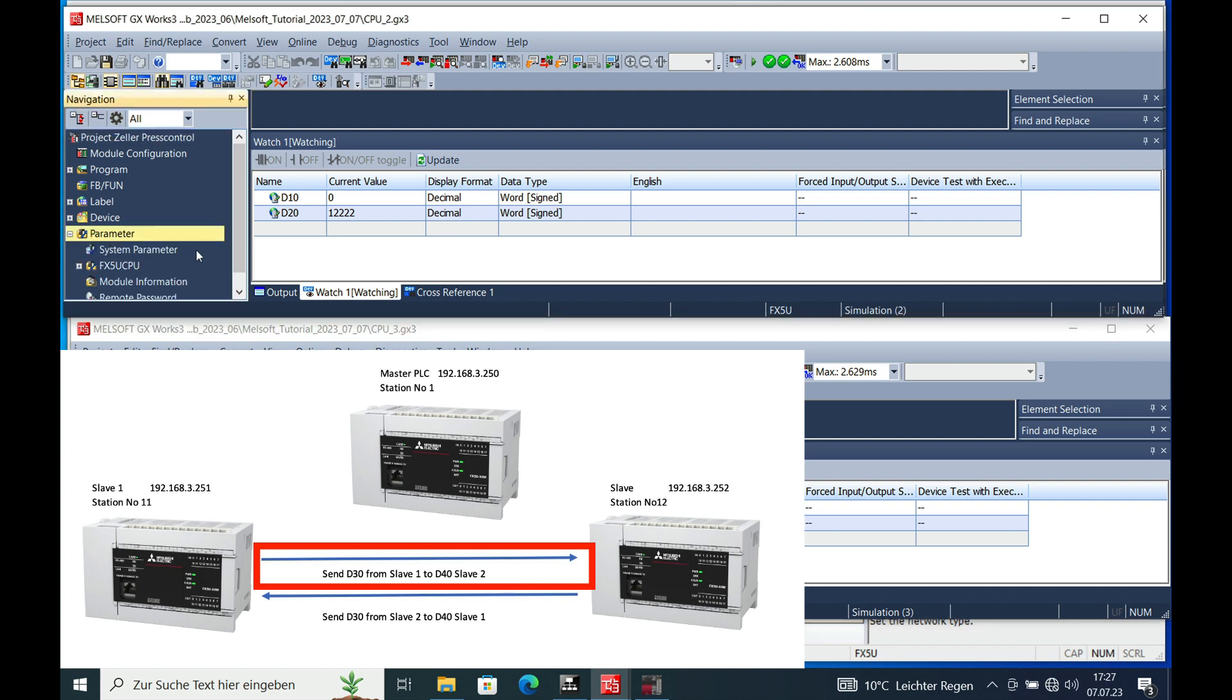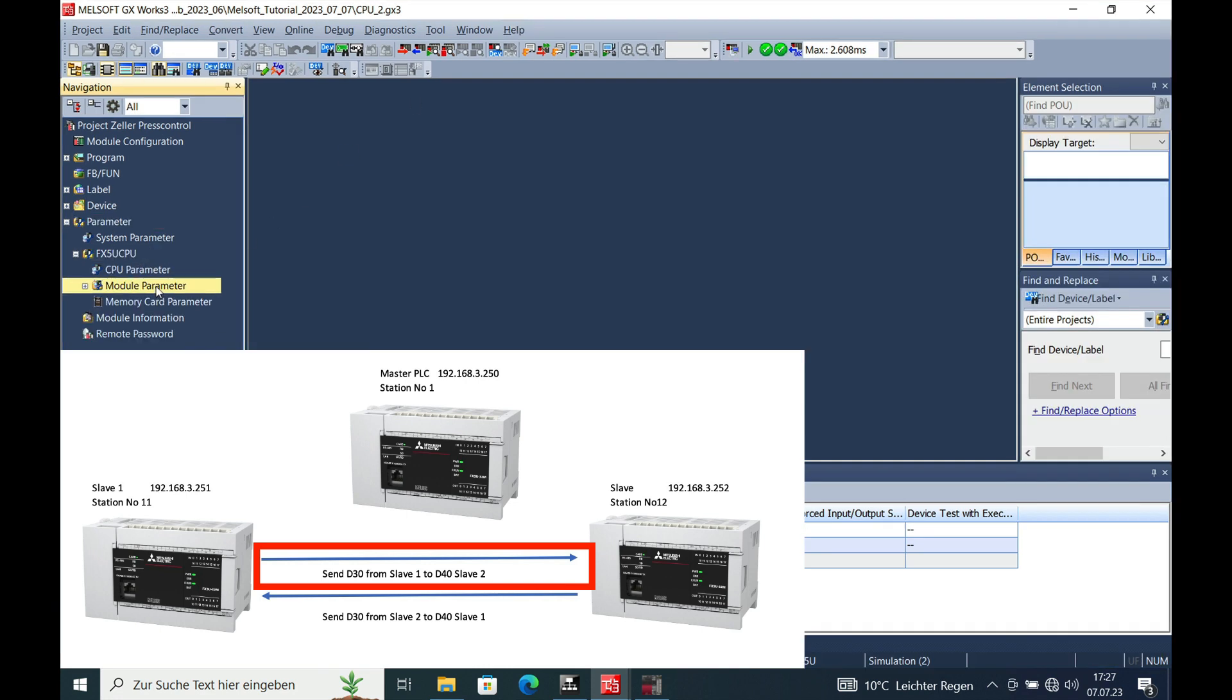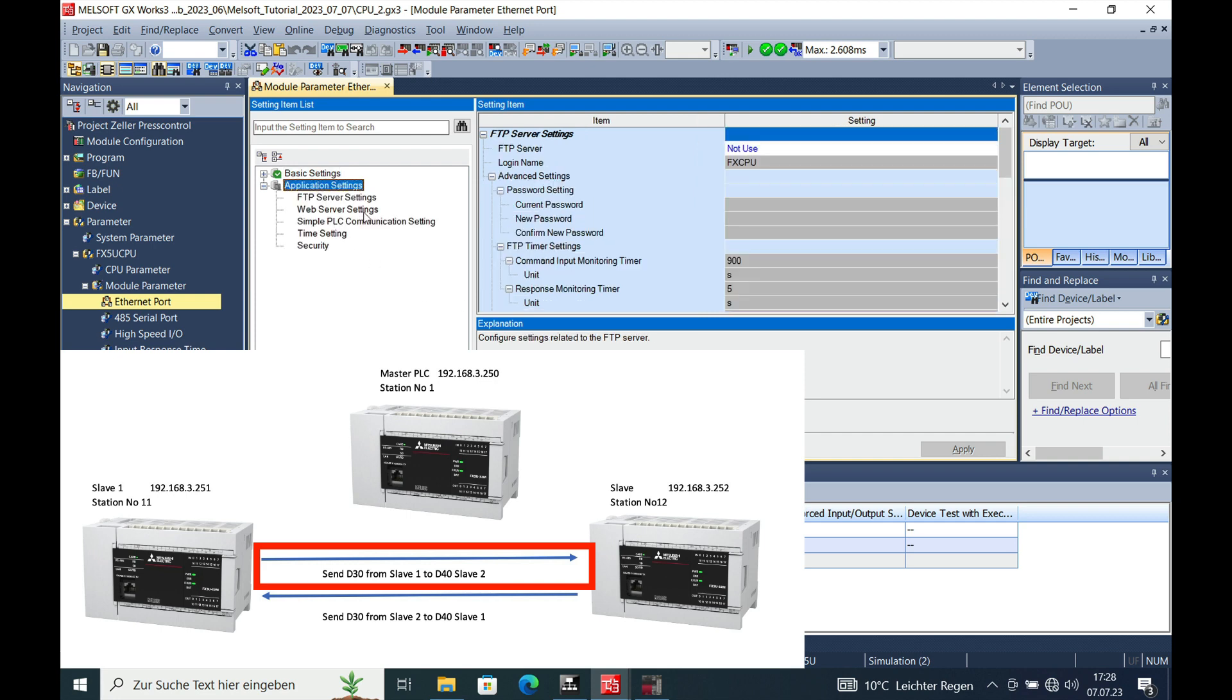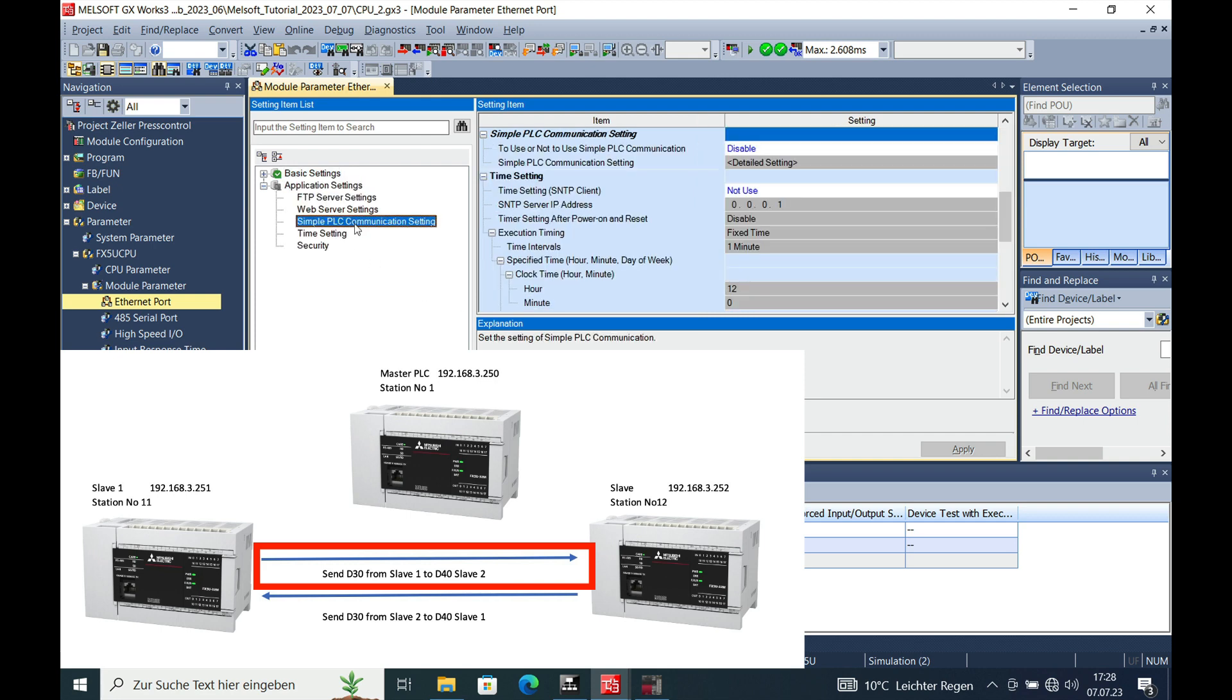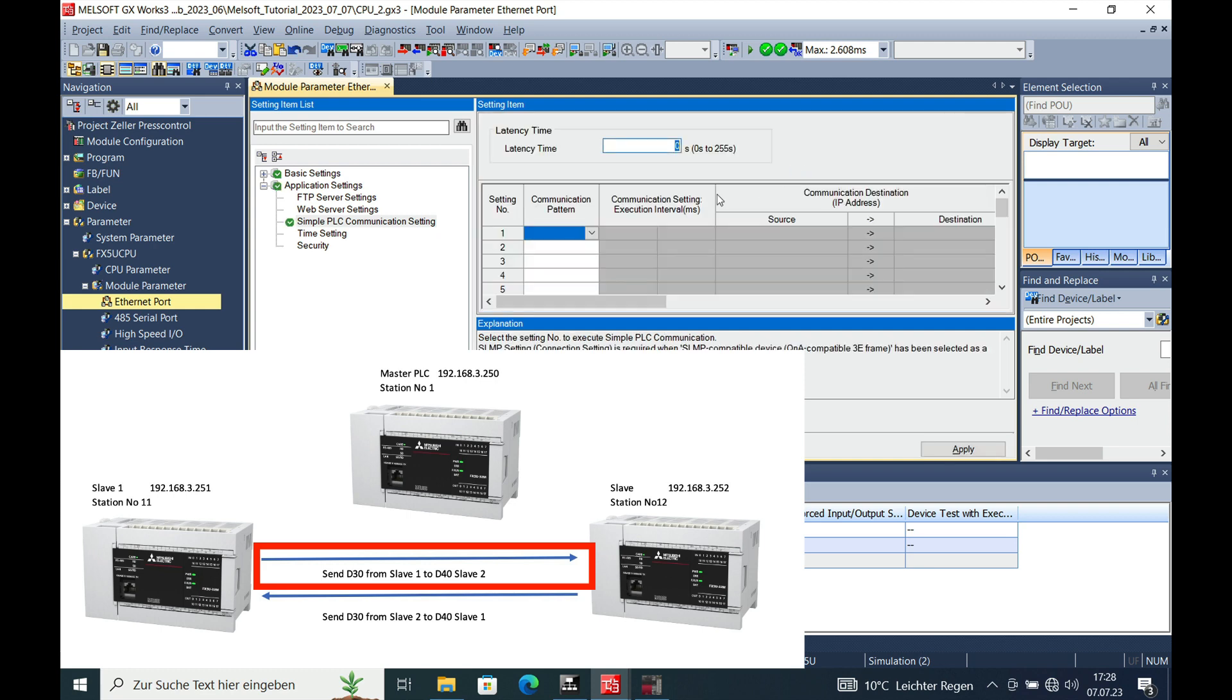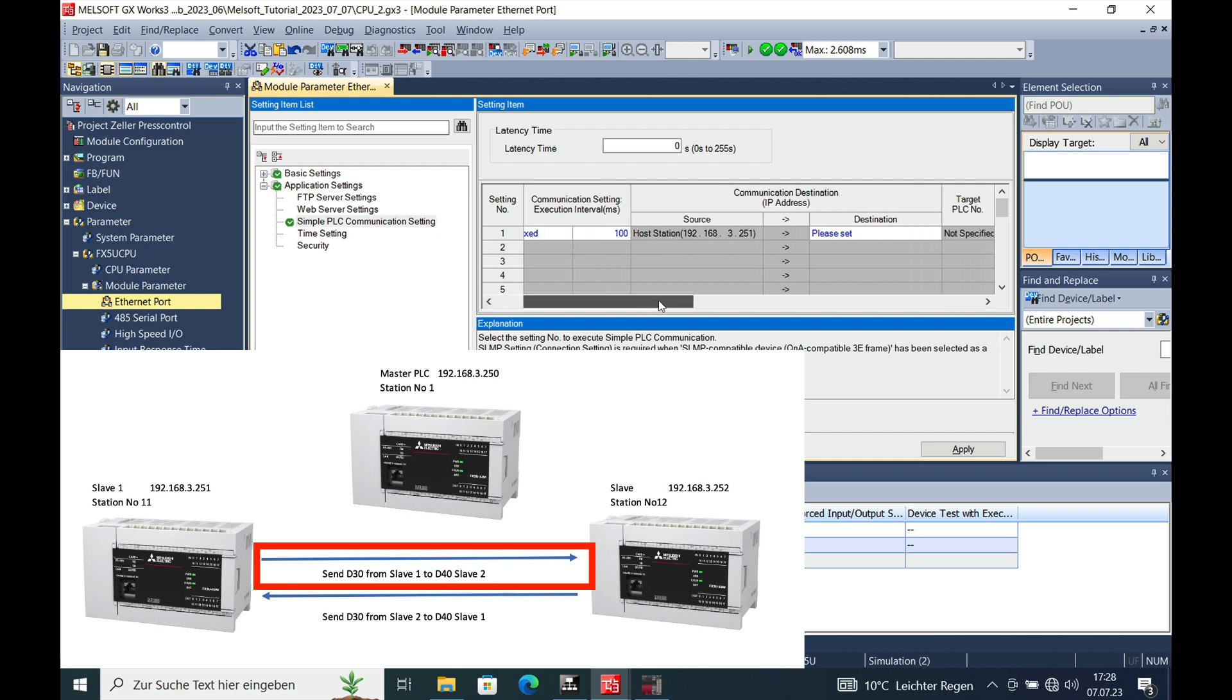Go to parameter, module parameter, Ethernet port, and then the application setting, the same thing like we did before. We make this enable and go to the details setup and we want to write from our host, from the source, which is our own CPU, the slave number 1, and we write through the Ethernet port to 192.168.3.252, which is slave number 2.